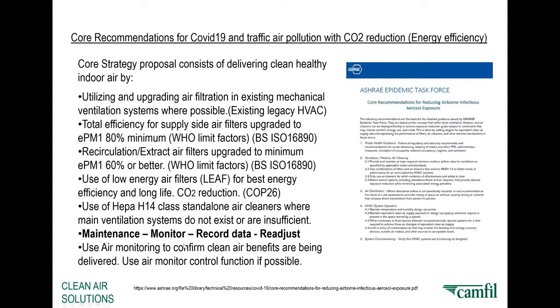Are they well sealed into the units, well engineered? Are they delivering clean air? Maintained so that they're not left to become over dirty, consuming heavy amounts of energy. They need changing, monitoring, changing when required. The data of the air, how clean it is, what the pressure drops are across the filter to make sure they're due or not due for change, should be constantly monitored. And then again, adjustments should be made should you find any problems based on the data.